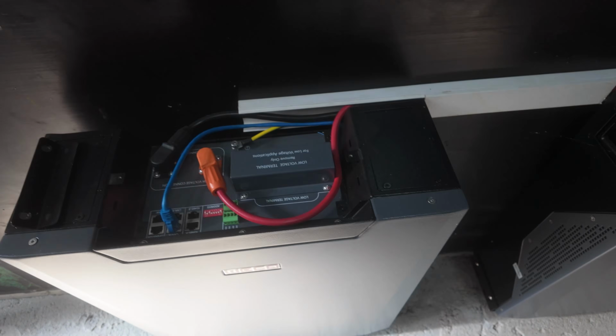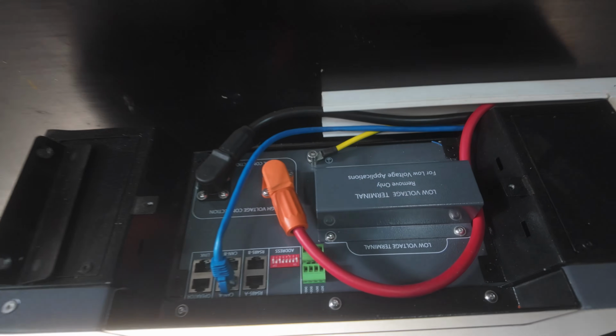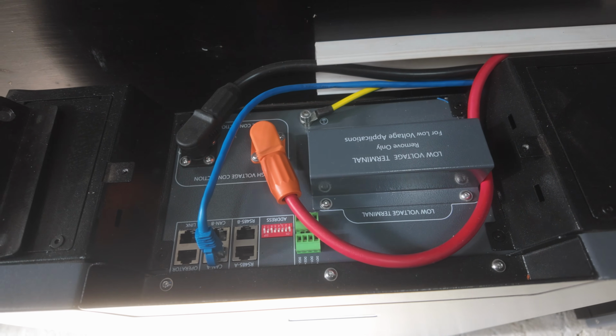They're a nominal 51.2 volt, fairly typical for a lithium-ion battery of this form factor, but they've got dual terminals - terminals for low voltage connection for paralleling, and terminals for high voltage connection so you can series them. You can series a lot of these together to get a high voltage string. We've only got 4 here, so we're running a 200 volt string. In series configuration, you have a string controller, effectively the BMS that manages the whole string.